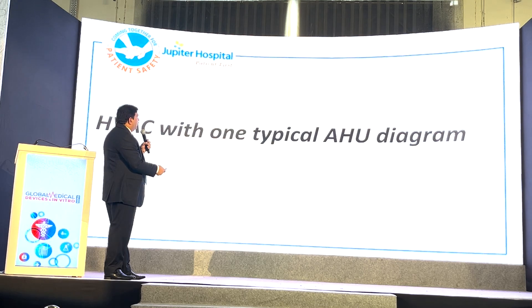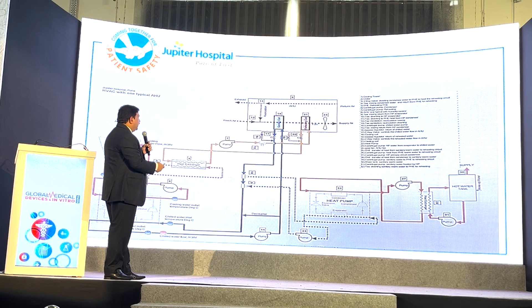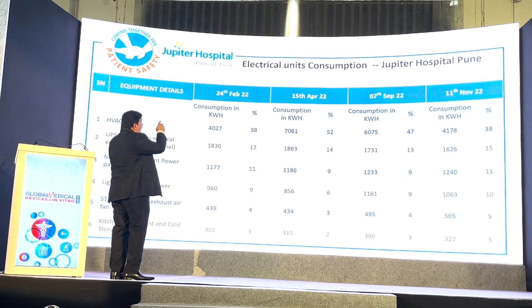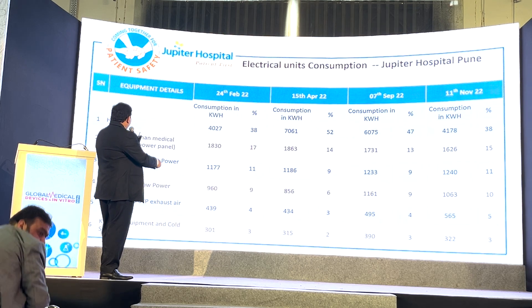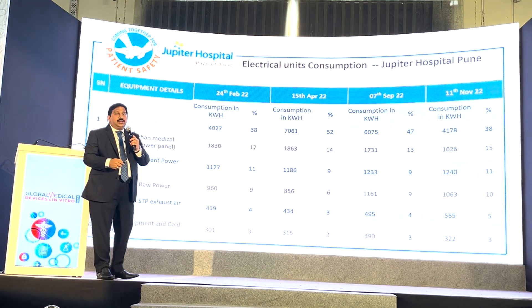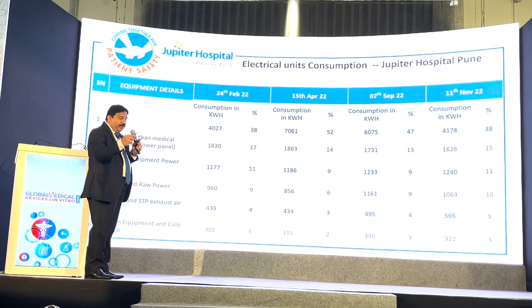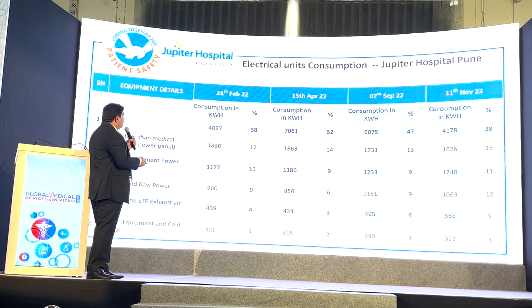This is our cooling tower performance. And the electrical unit consumption — you can see what we have done in February, April, September, and November. For HVAC, in Thane it was somewhere around 8,000 to 9,000 units. Now it has come down to 4,027 and 4,178. If you were talking about 54% or more savings there, here only in April it was 52%, otherwise it is 38%, 47%, 38%. These are the readings taken for cooling.